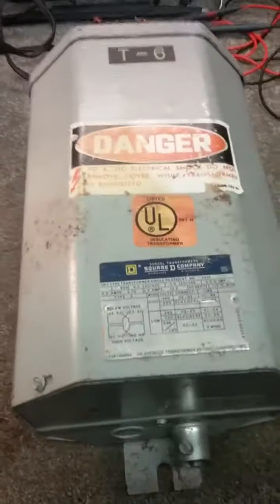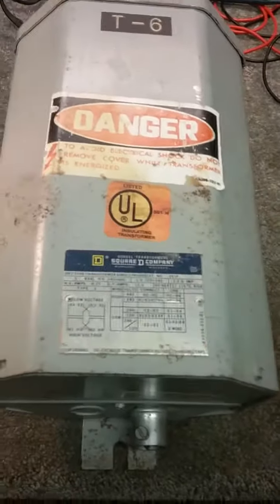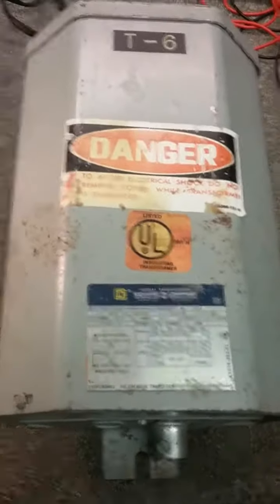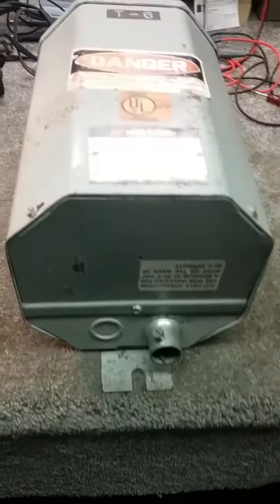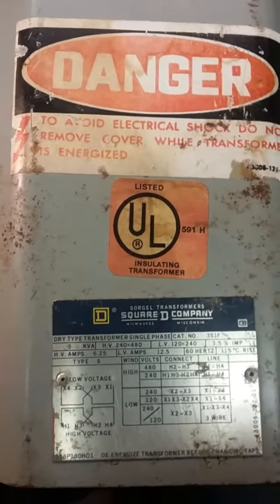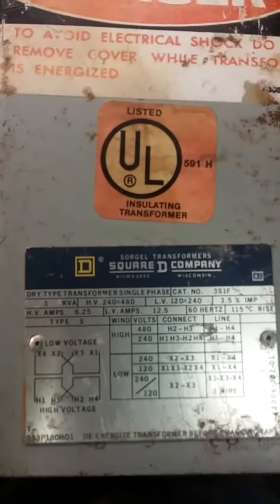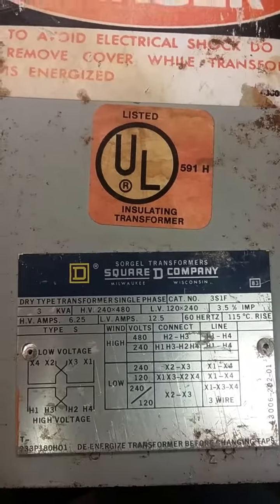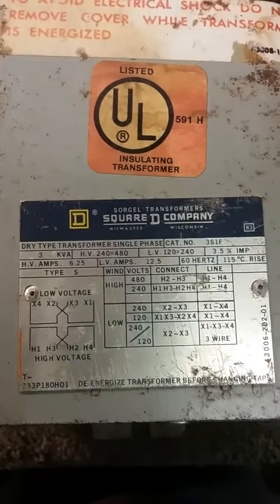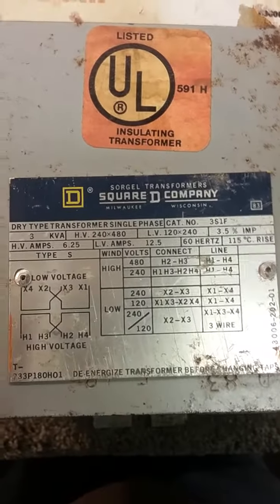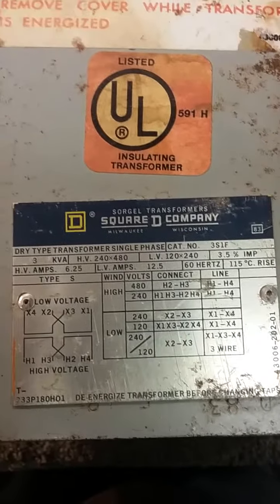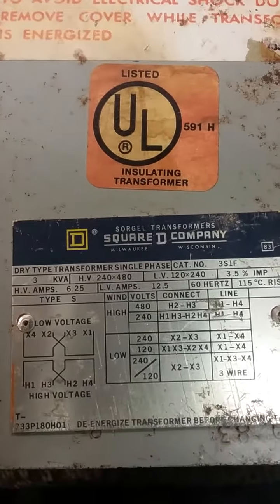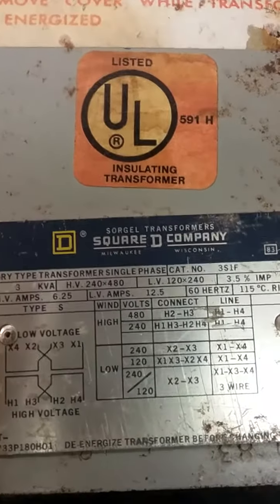Hello, this is Paul here, and today I'm going to be looking at this transformer I picked up locally. It's a power transformer, and it's a 240 volt step down to 120 volt. It's a 3S 1F type transformer. And so that means that it's 3,000 volt amps, or 3 kVA, and it's a single phase unit.